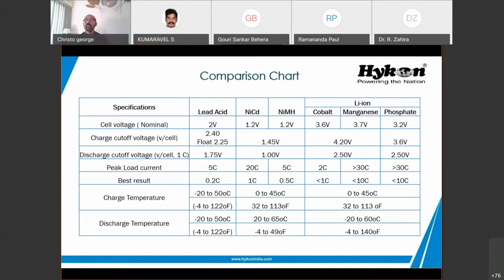Not a peak, but if you look at a continuous discharge, which normally in lead acid is not possible, it can discharge continuously to a maximum of 0.2 to 0.3. But in lithium, you can continuously discharge. It depends on different type of chemistry, and within the same chemistry you can have cells of different C rating, but you can go very high discharge, even 10C. That means if it's a 100 Ah battery, you can discharge 1,000 ampere from that cell when we are talking about a 10C battery.